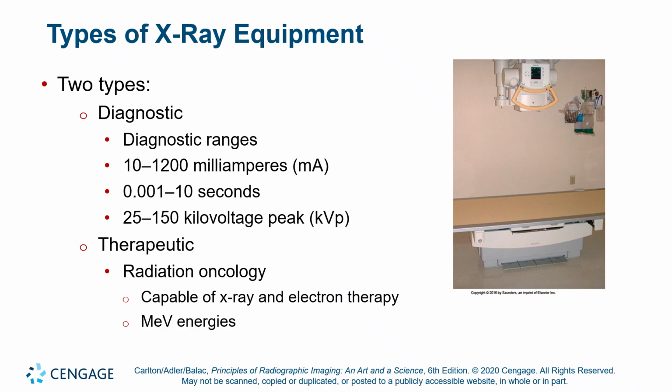So 150 is a little bit extreme as far as what you need for most folks. I can count on one hand the number of times I went north of 130 kVp for a technique. So, all right, yeah, that's our capacities for our generator and our timing circuits, and for our tube current.